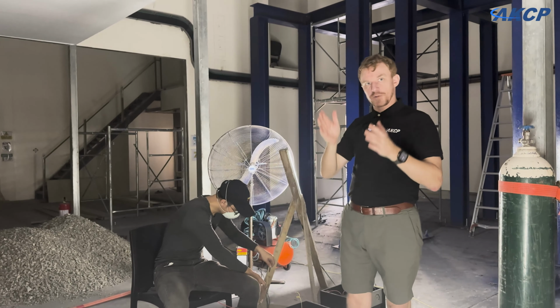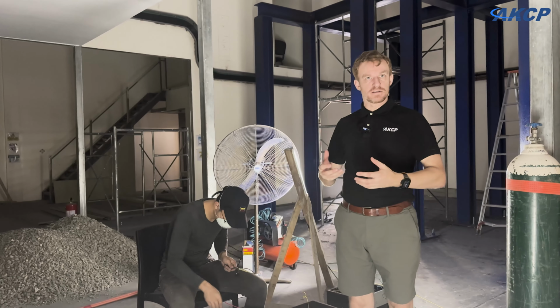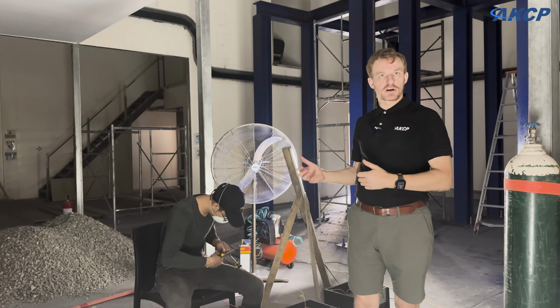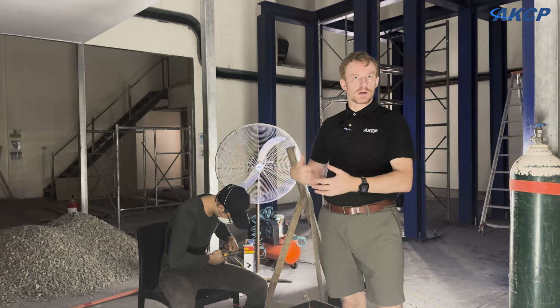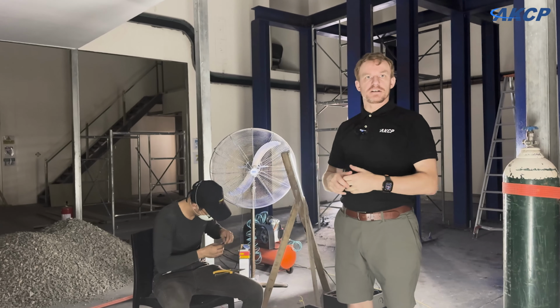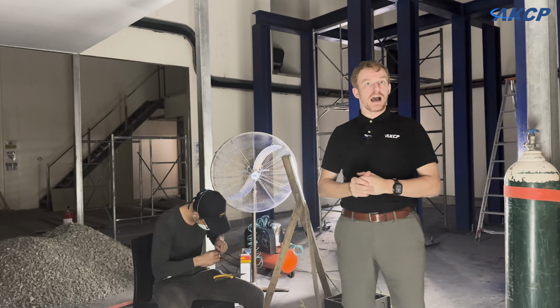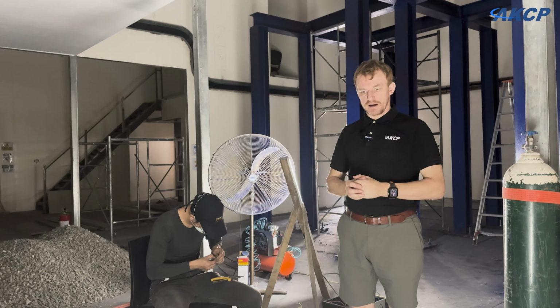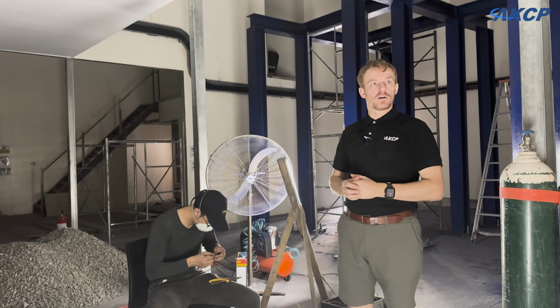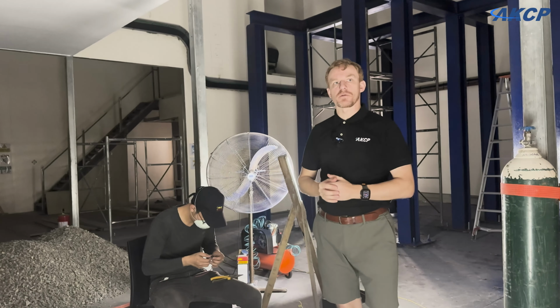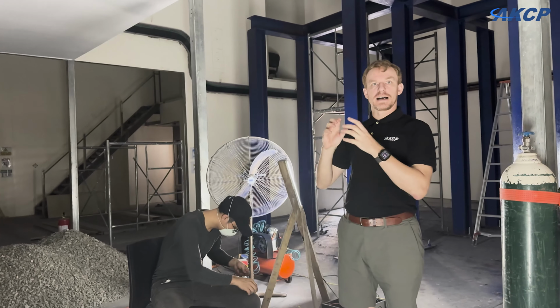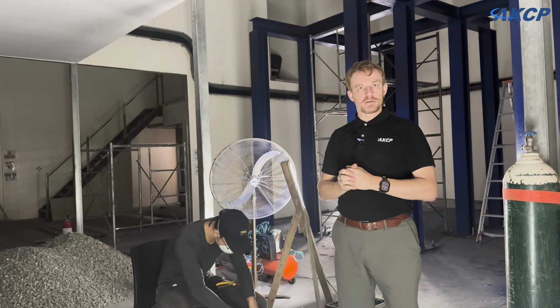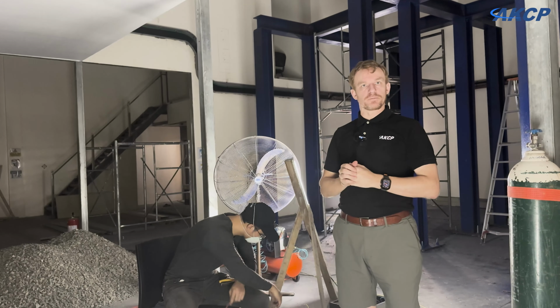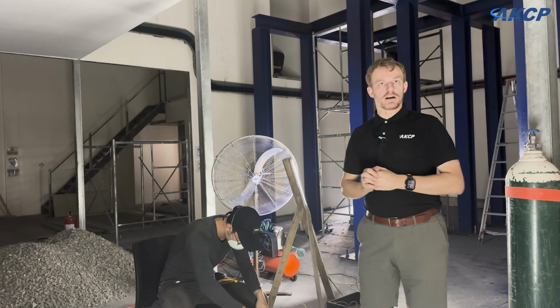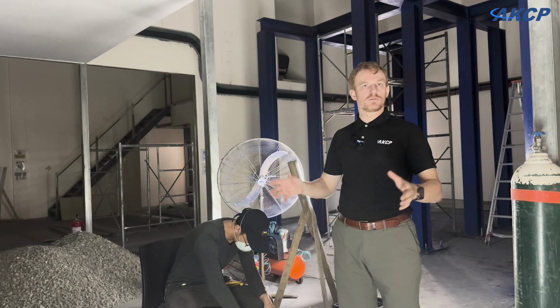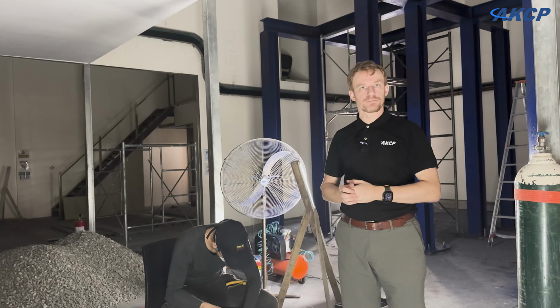In addition to that, on the front of the racks, we've got some fans, and those fans are going to be pulling the cold air across these heaters, cooling them down, heating up the air, which is obviously simulating what would be happening with servers. Those fans are 3-phase, so we have 3-phase power coming into the breakout boxes. We're modifying those to add a single 3-phase socket that we can connect the fans to. Let's go and take a look at one of the racks and how this looks when it's actually assembled.